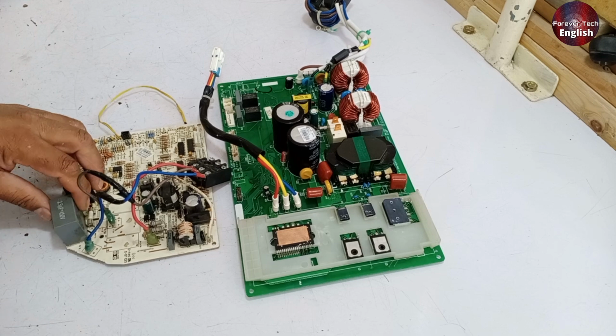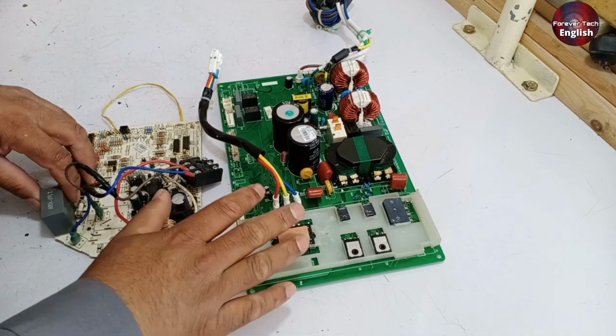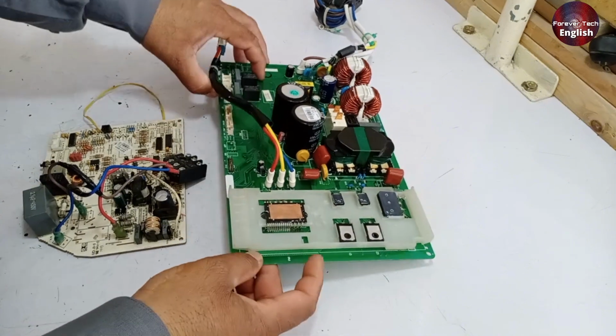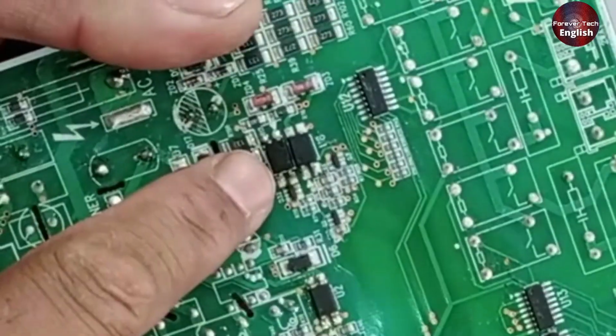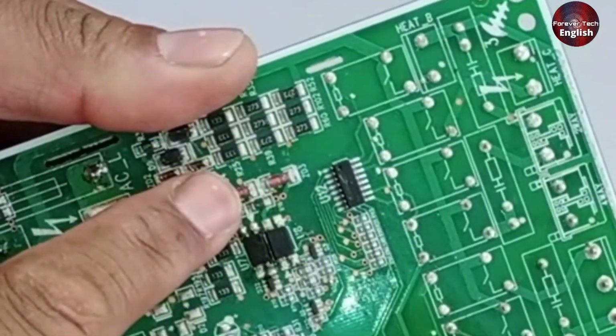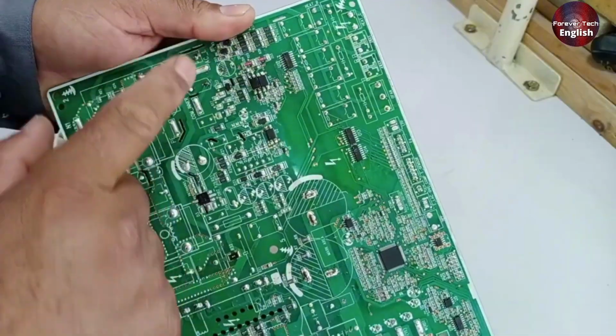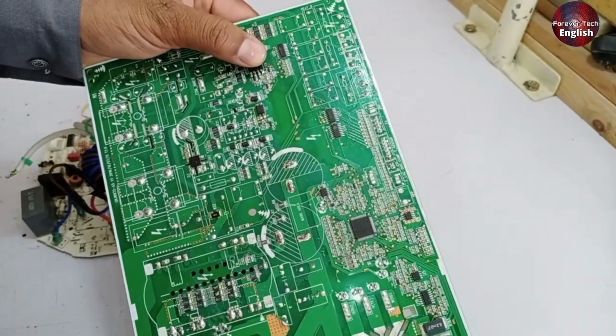So, let me explain what we have done with this PCB to resolve the issues. First, we addressed the E6 communication error. To fix this, we replaced the optocoupler and also changed 2 diodes. After doing this, the communication system was restored and the error was resolved.